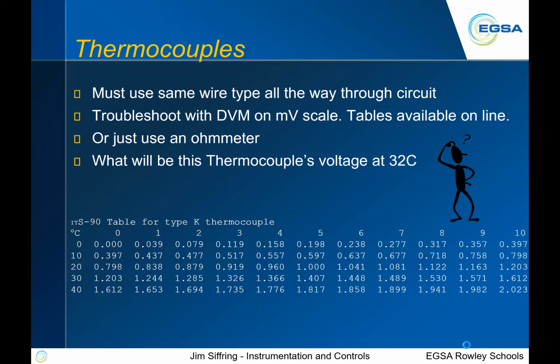Really easy to troubleshoot with the DVM. You can't really read the voltage on it because they're actually millivolts. So you have to have some kind of a device that's designed to read a J-type thermocouple or a K-type thermocouple or whatever thermocouple you have. But if you isolate it and put a DVM, digital voltmeter, on it and put it on ohms, it's really easier. You just measure it, and if it's got resistance, or it looks mostly like a short, really, it looks almost like there's very little resistance on that wire, it's probably good. If it shows open, then it's no good.